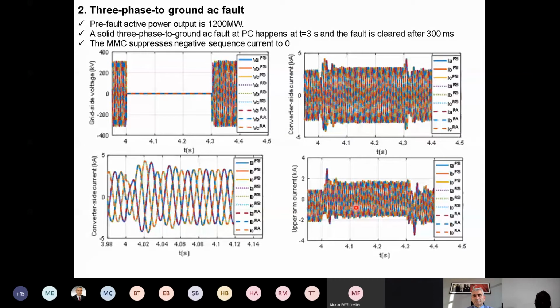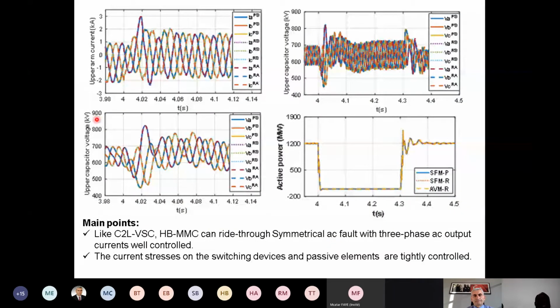Why do we display that one? Because this current contains the AC current and DC current, which can all be seen in the arm current. You can see both of them well controlled. And here is the zoom of the arm current around the fault instant. Also, all the models appear almost similar. And these are the capacitor voltages, as a sample of the upper arm capacitor voltage from all these models. They also exhibit a little bit of short disturbance. And here is the zoom of this, and this is the drop of the active power to zero as the voltage dropped to zero at the PCC.